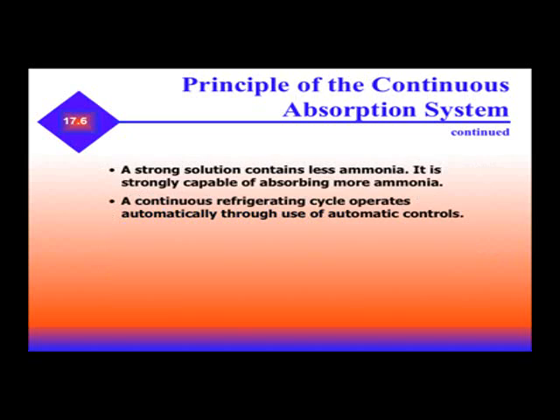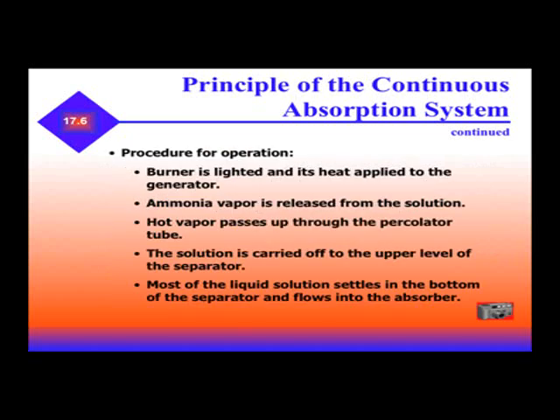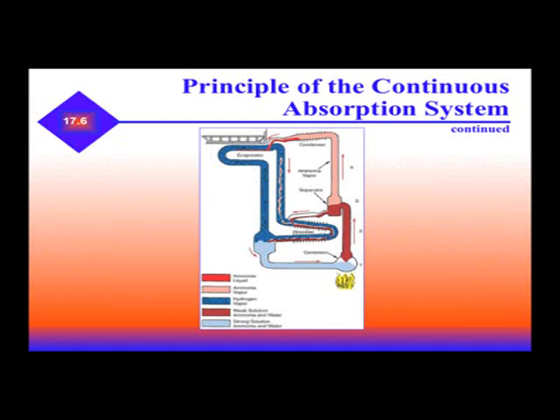A continuous refrigeration cycle operates automatically through the use of automatic controls. The sequence of operation: the burner is lighted and its heat is applied to the generator. Ammonia vapor is released from the solution. Hot vapor passes through the percolator tube. The solution is carried off to the upper level of the separator. Most of the liquid solution settles in the bottom of the separator and flows into the absorber. The liquid mixture rises, the ammonia vapor separates off and goes into the condenser. The liquid goes into the evaporator, mixes with hydrogen in the opposite direction, and as it boils off back into vapor, we absorb heat.